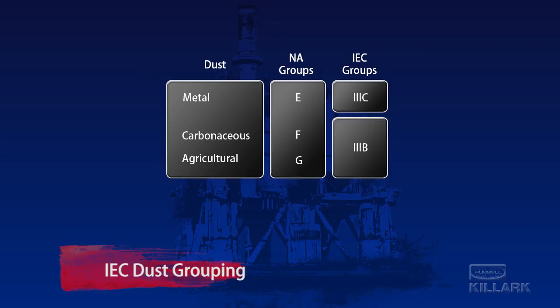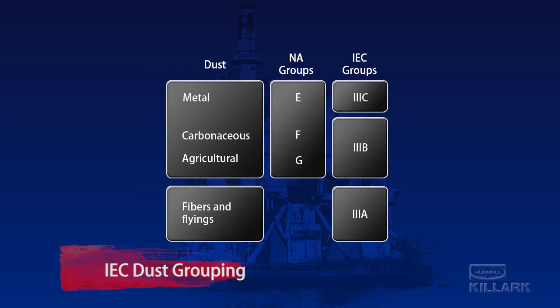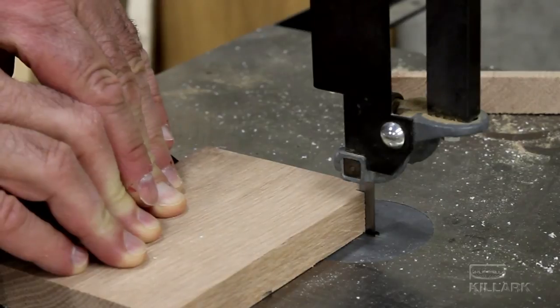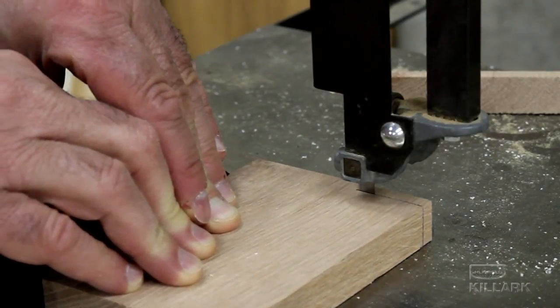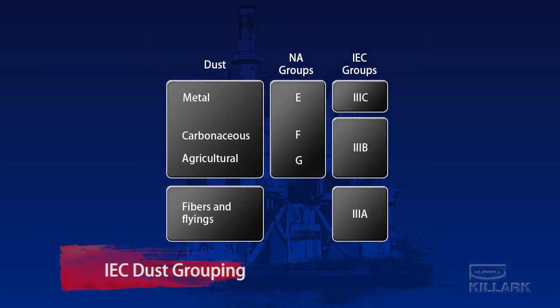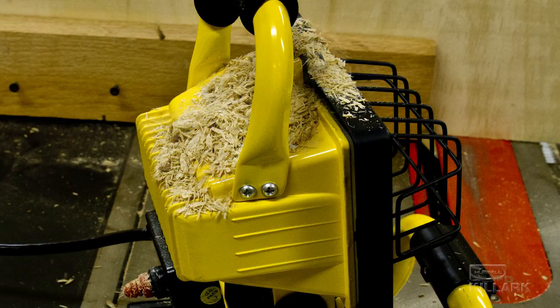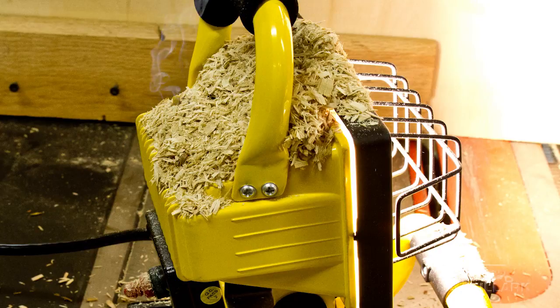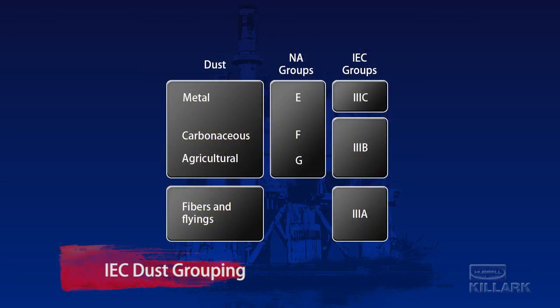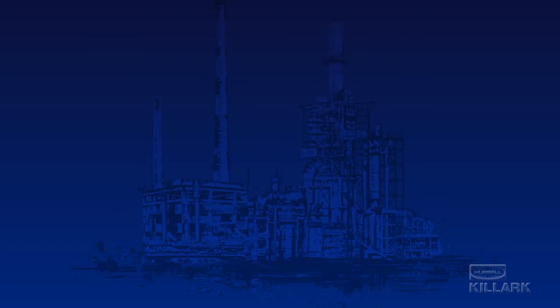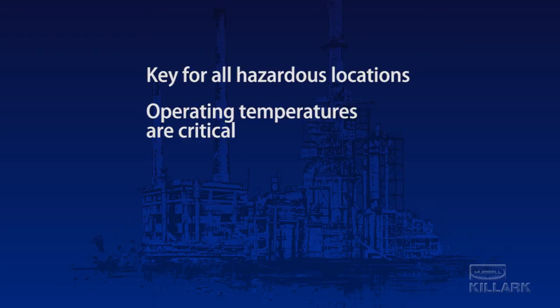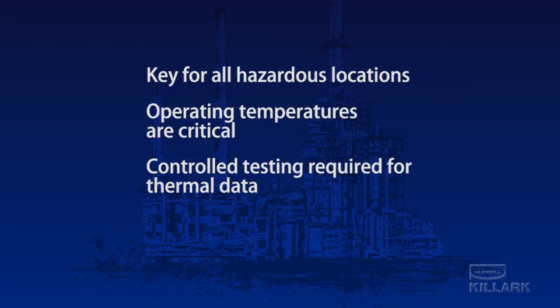Rather than finely pulverized dust, IEC Group 3A contains flammable fibers and flyings that might, for instance, be found in a woodworking plant or a textile mill. In these situations, the concern is more about an easily ignited and rapidly burning fire than an explosion. The buildup of fibers and flyings on electrical equipment might result in elevated temperatures that could be high enough to initiate an unexpected fire, or even lead to spontaneous combustion as the material ages under thermal stress. This particular IEC group incorporates and consolidates the North American treatment and classification of fibers and flyings known as Class 3. As with all aspects of dealing with hazardous locations, temperature information is critical to the risk management process and product selection. Controlled testing provides the essential data on the thermal behavior of the equipment.